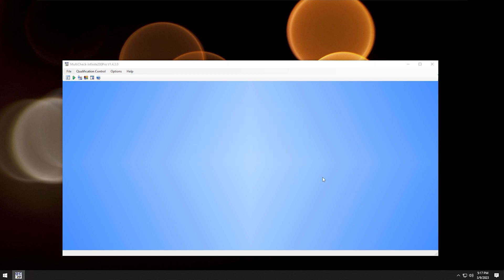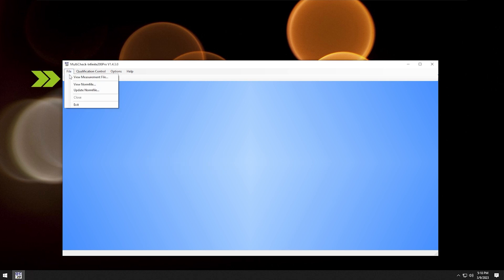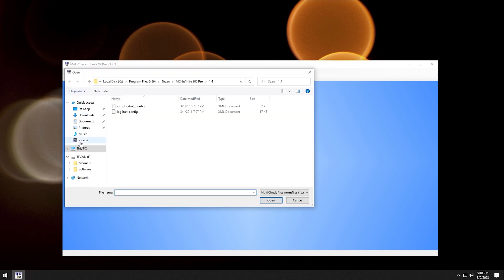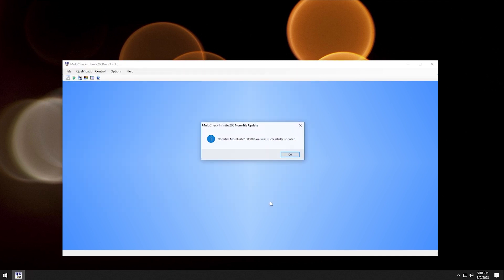After the login, you have to add the norm file to the program. The norm file contains the data against which your reader will be compared. Click file, then update norm file. On the TECAN USB stick, click on the norm file and open it. Click OK.